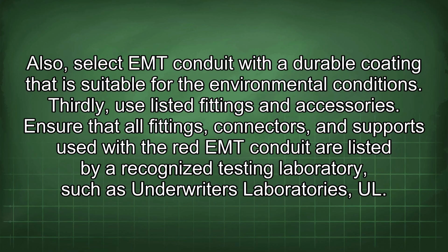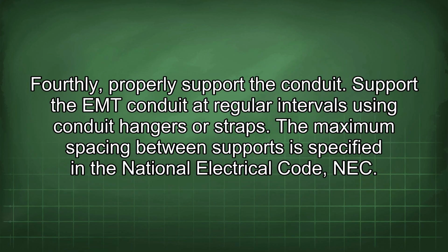Thirdly, use listed fittings and accessories. Ensure that all fittings, connectors, and supports used with the red EMT conduit are listed by a recognized testing laboratory, such as Underwriters Laboratories, UL. Fourthly, properly support the conduit. Support the EMT conduit at regular intervals using conduit hangers or straps. The maximum spacing between supports is specified in the National Electrical Code, NEC.